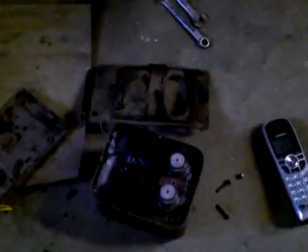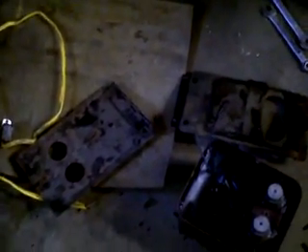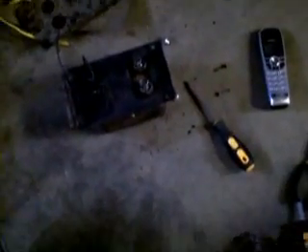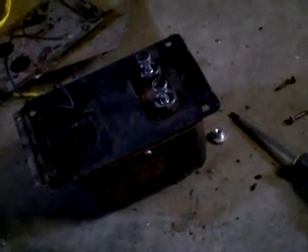All right, so a quick update. I gave my father a call, who used to work on these transformers and old furnaces for quite a few years, and he told me that these things just have a frame on them. He said take the screws out around the perimeter and switch frames, and it'll bolt right onto your furnace. So I switched the frame over, and I discovered that I could also switch the springs over as well. Wasn't that big of a deal. So the springs are now on the transformer that works, and I'm about to bolt her up and flick her on. So that was a very good phone call to my father.